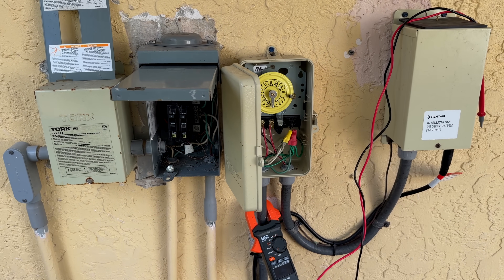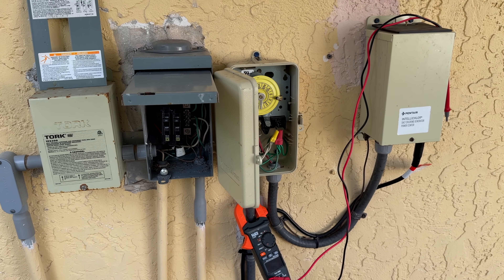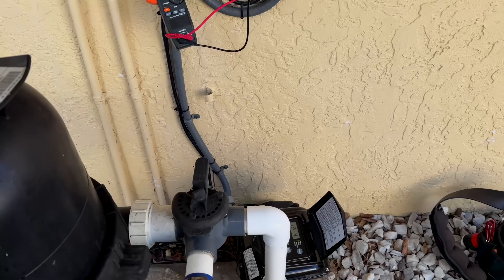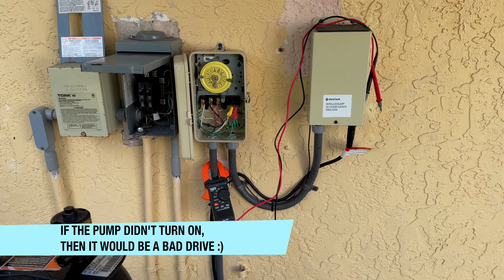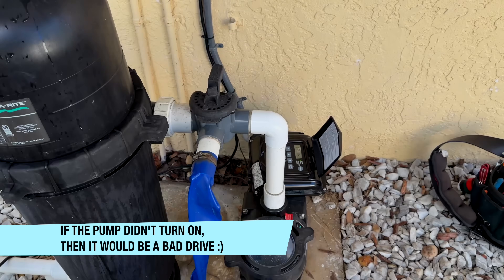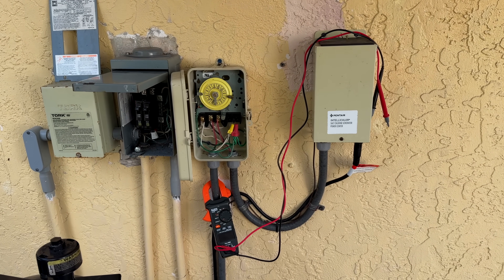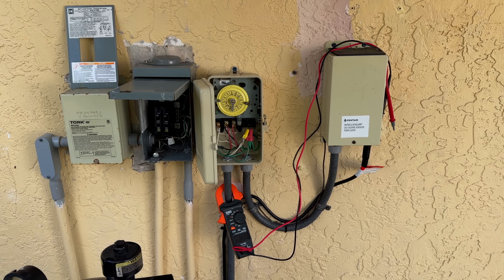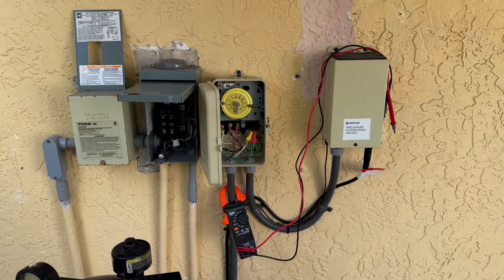Unfortunately an electrician has to get involved — I've gone as far as I can. I just want to show you this uncommon electrical issue that's causing this pump to throw that error code, because typically you'd just throw a new pump in and be on your way. But if you did that in this case you'd end up with the exact same issue, because it's not a pump issue — it's an electrical issue. I hope this video helps you be more efficient and precise when doing your electrical diagnosing.